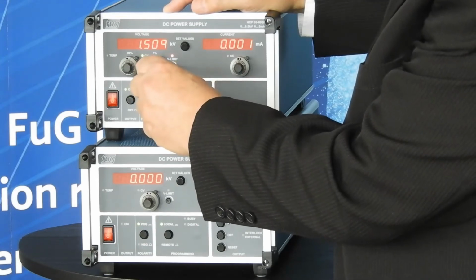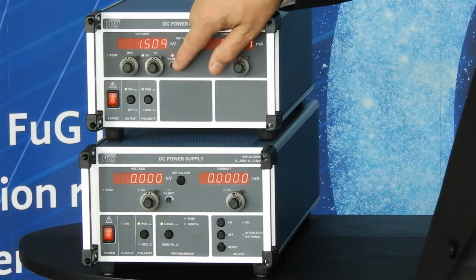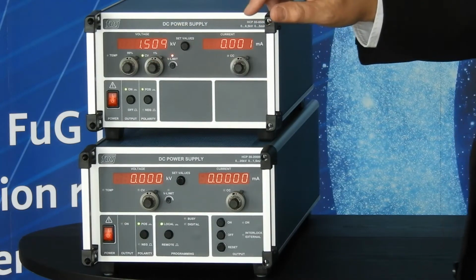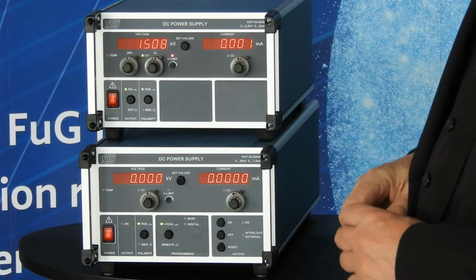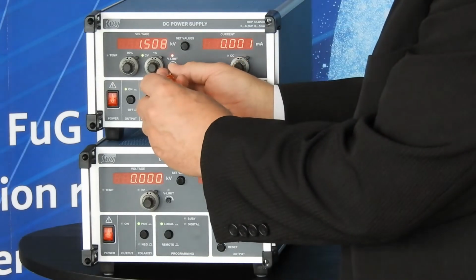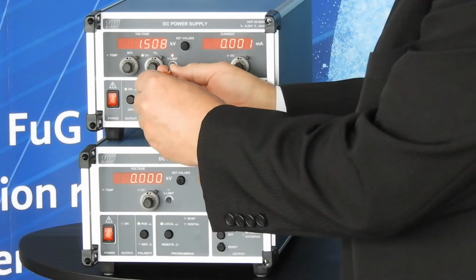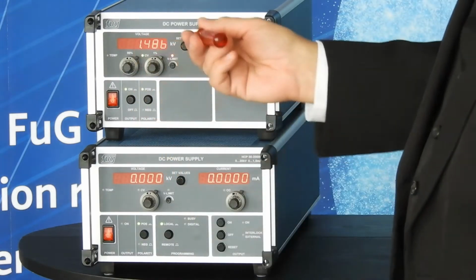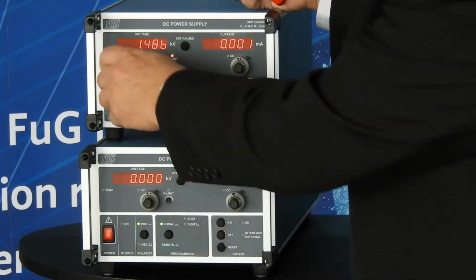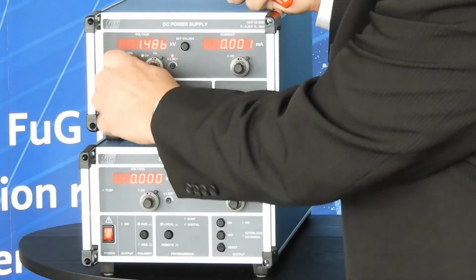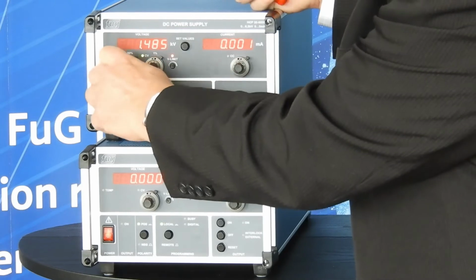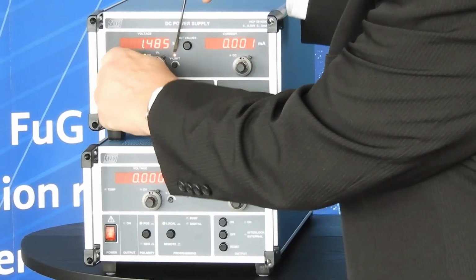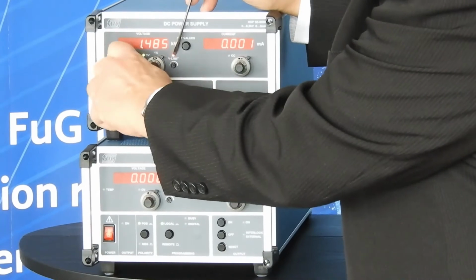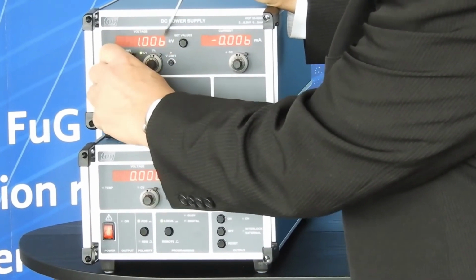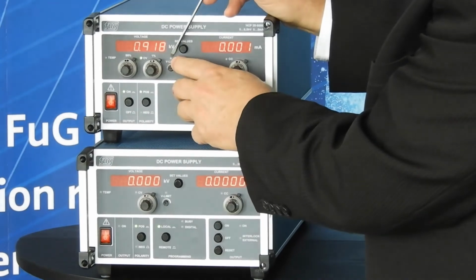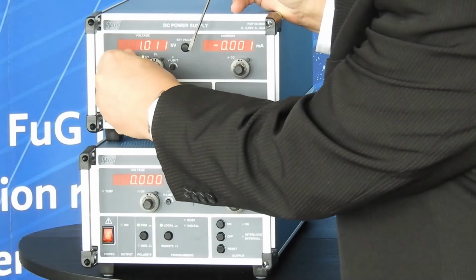I will set 1500 volt. This potentiometer is not as accurate as the 10-turn potentiometers, but it allows you, if you don't want your voltage to go higher than 1500 volt, to set it to about 1486 for example. Now you can adjust the 10-turn potentiometer as you want, and as long as the red LED is on, the voltage will not increase anymore. If you go down, the red LED goes off, and now you can adjust the voltage.